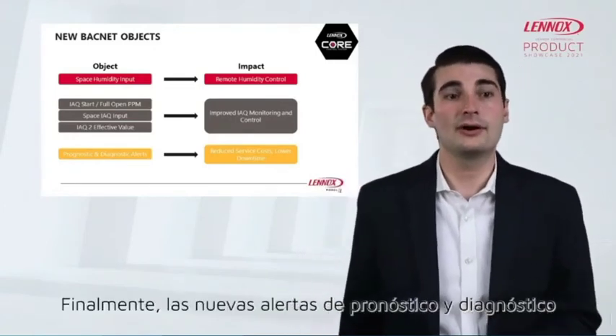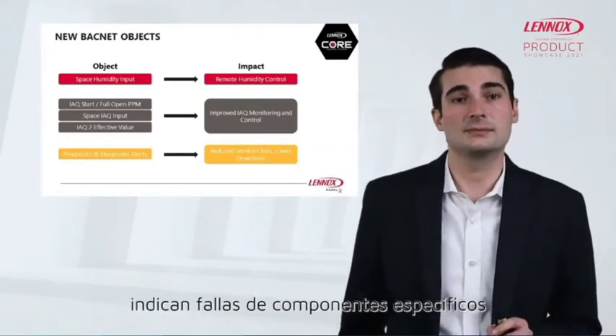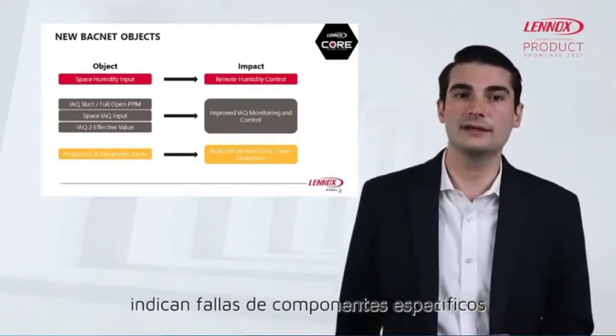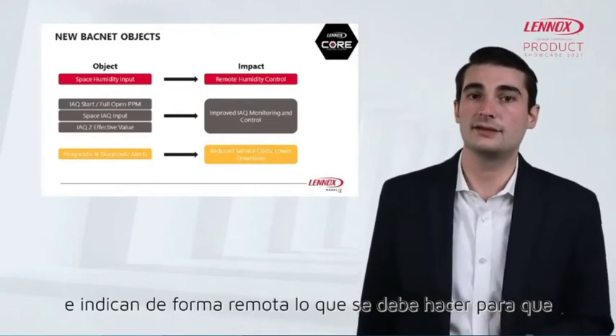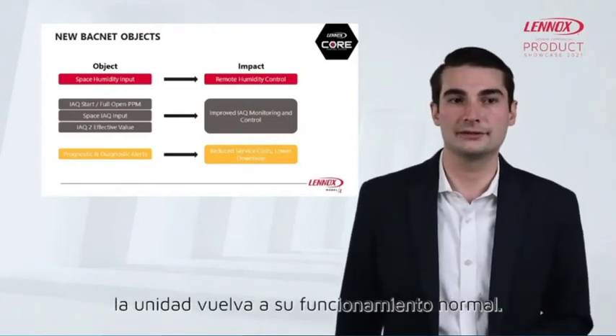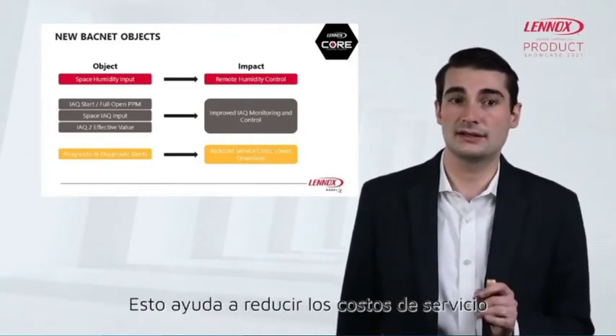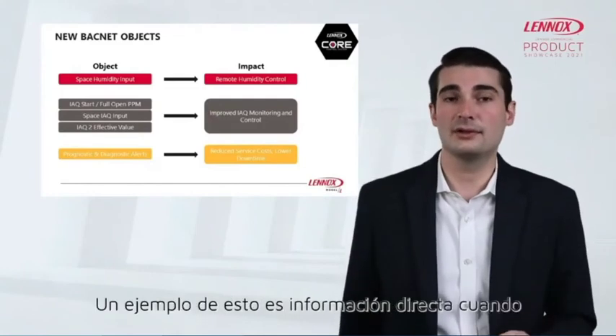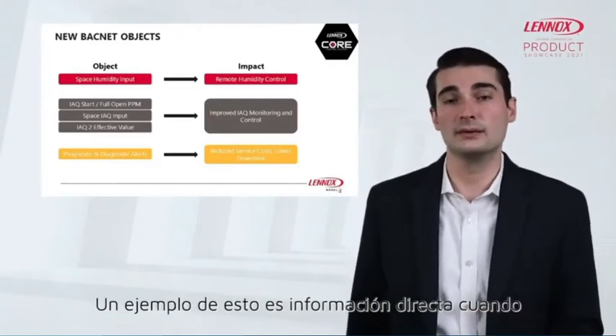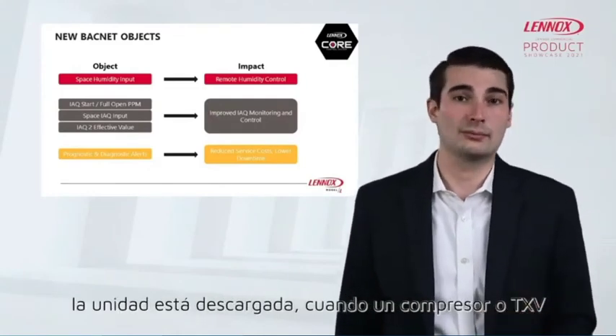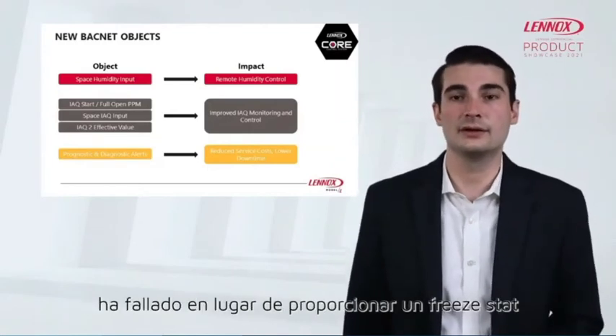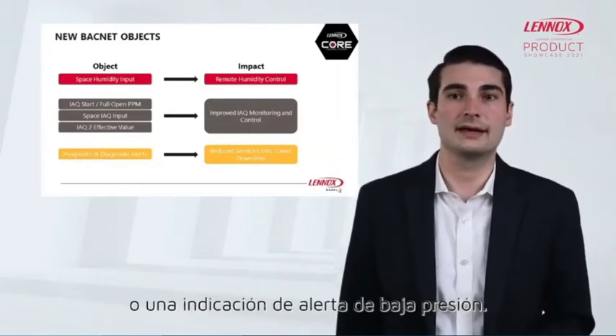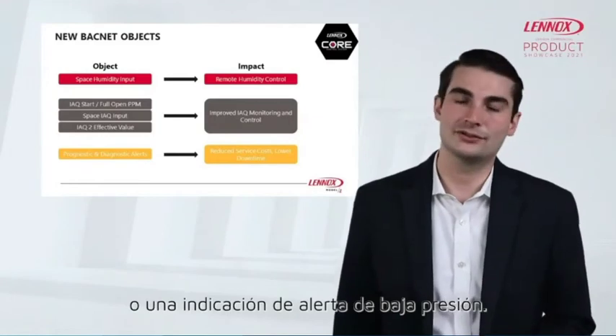Finally, the new prognostic and diagnostic alerts indicate specific component failures and remotely indicate what needs to be done to get the unit back to normal operation. This helps to reduce service costs and lower downtime. An example of these is telling you directly when the unit is either out of charge, when a compressor or a TXV has failed, rather than providing a freezestat or low pressure alert indication.